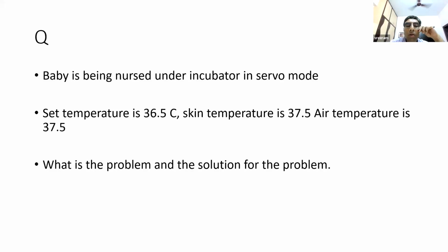It's basically because the probe is dislodged. That is why you have the skin and air temperature being the same. The probe is lying on the baby's bed. Understand? So that is why you have a similar reading of both. Okay, so if you have such a display, always look at the baby, check whether the probe is attached, and attach the probe properly. I think that's it.